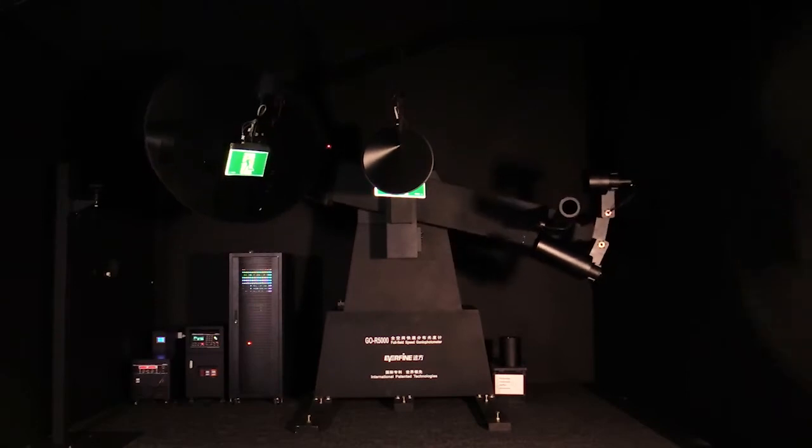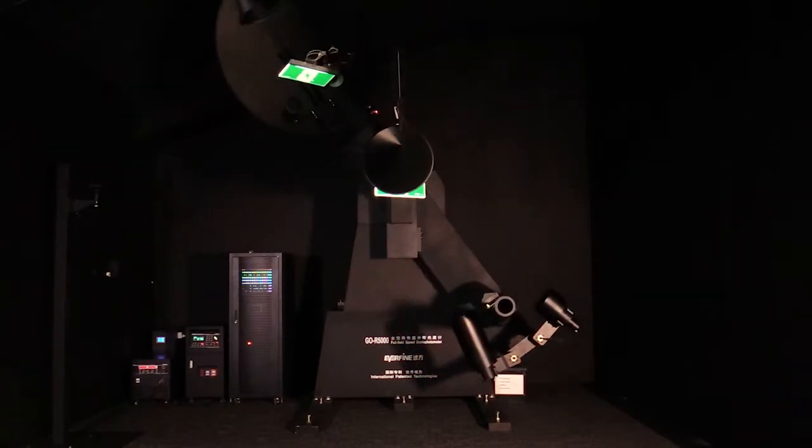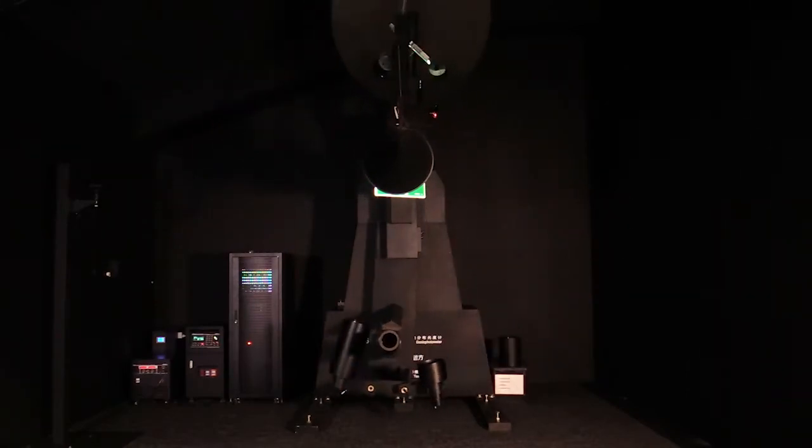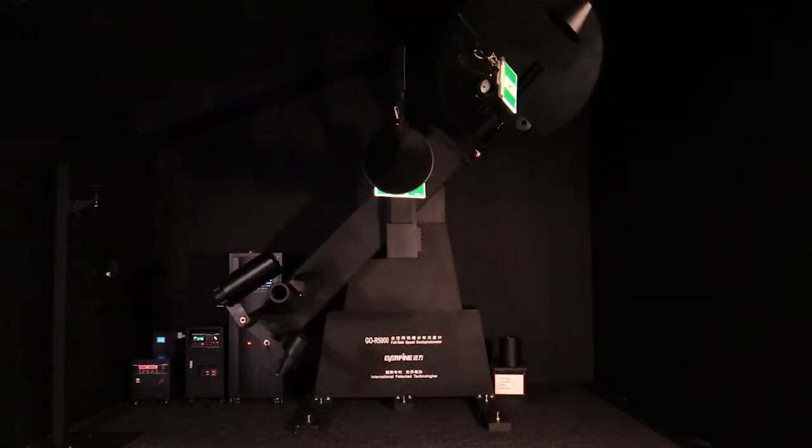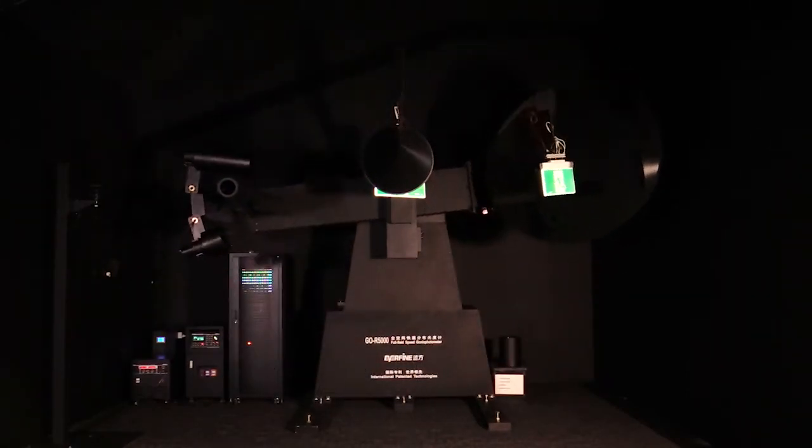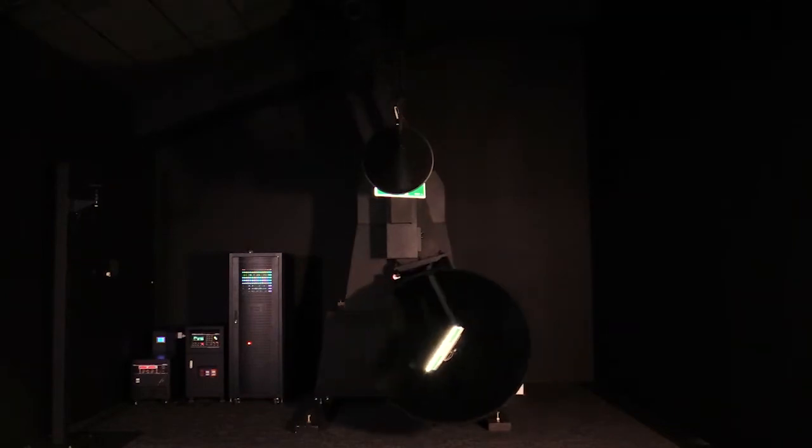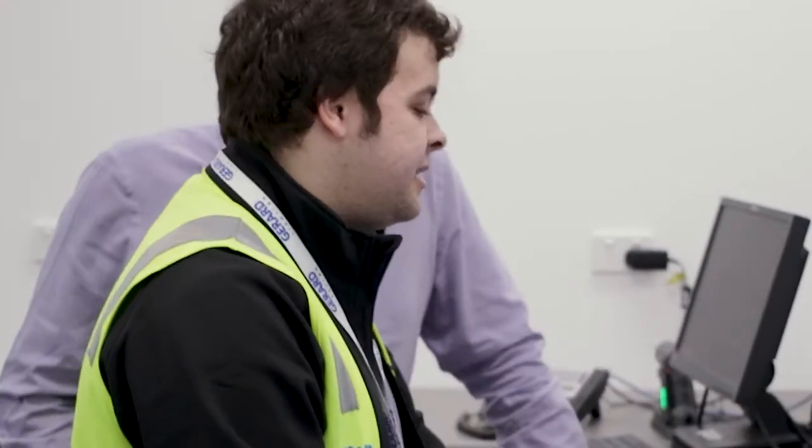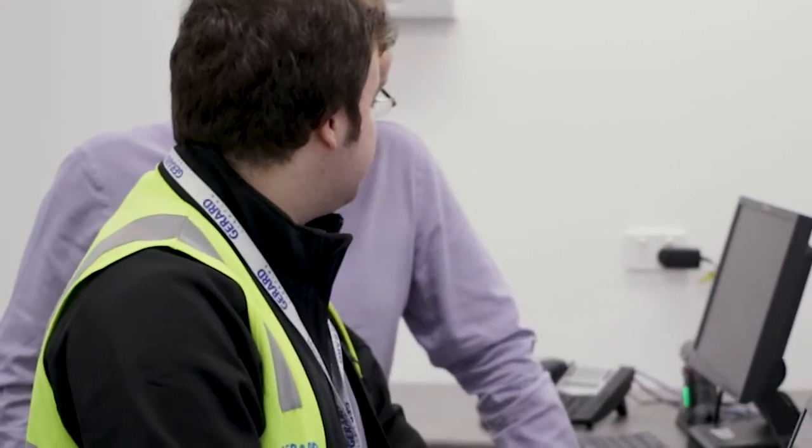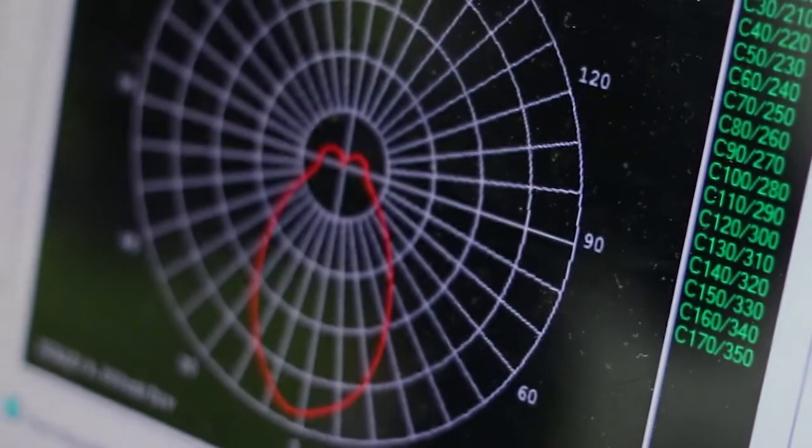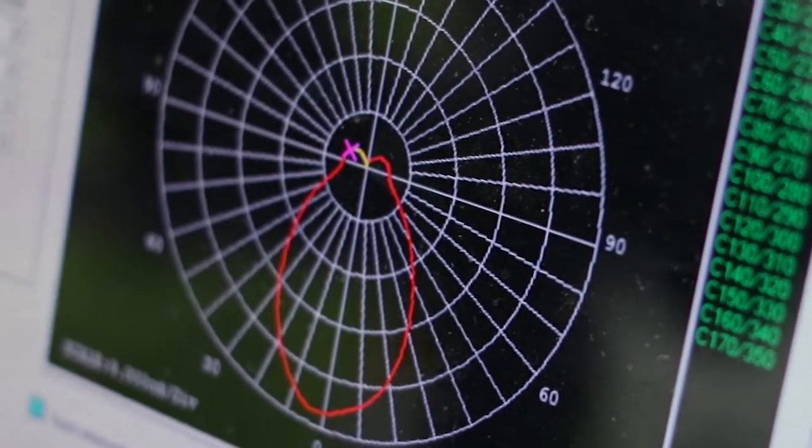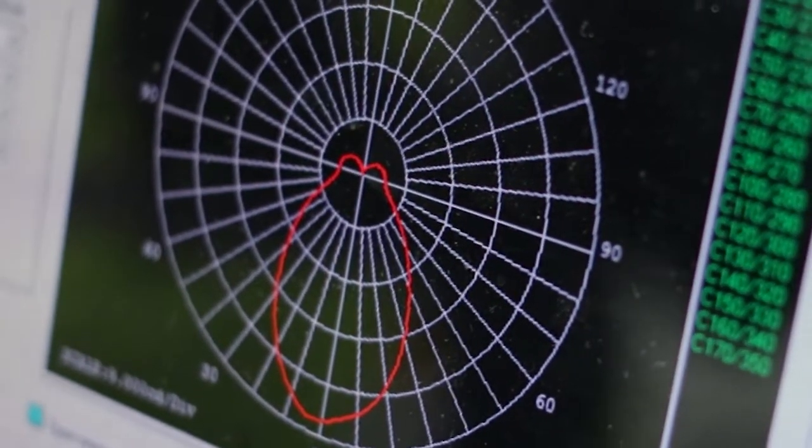As that rotates around it's changing the angle that that cell is viewing that luminaire. So we are now physically getting a measurement from every point within that luminaire that generates the IES file.